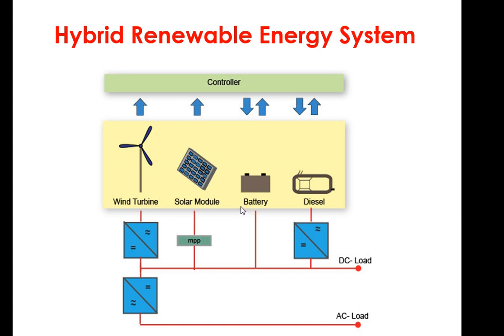One thing that you will take care of: suppose this inverter is 3-phase, and we are considering the various operations of the 3-phase inverter at some typical line to line voltage of 440 volt, and the single phase is of 325 volt DC. It means that if a single phase source is of 230 volt AC, then I should try to operate this bus at 325 volt.